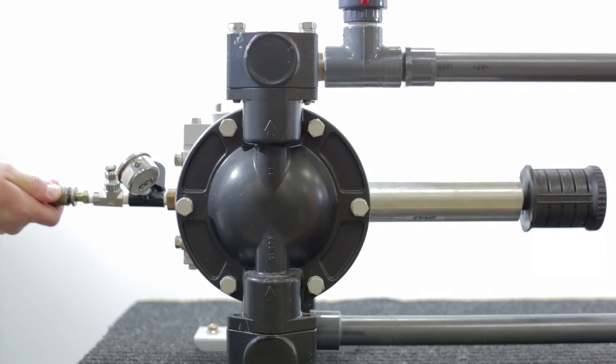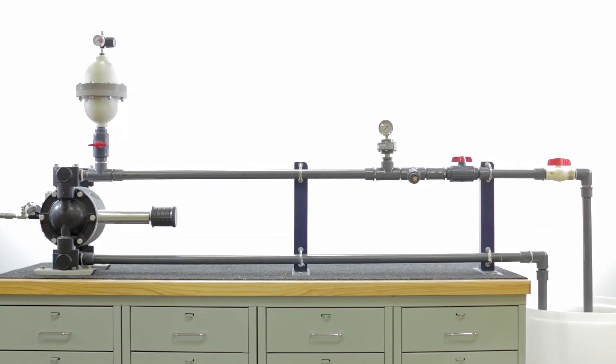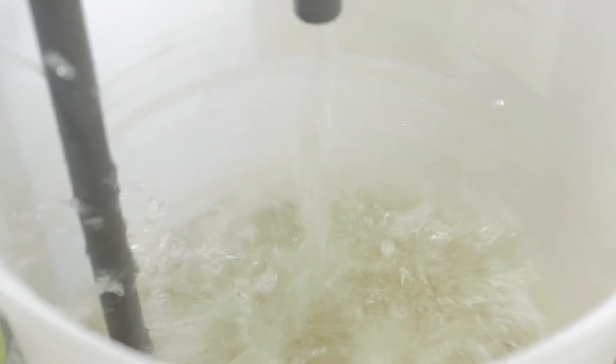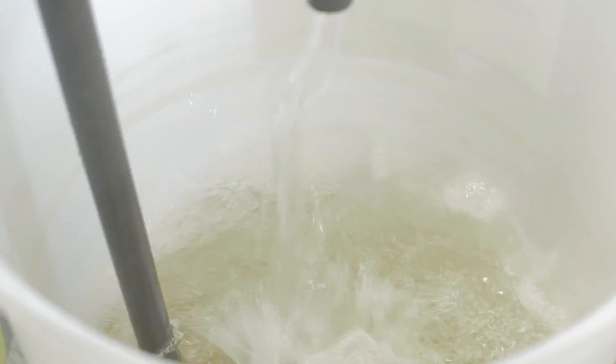When I turn the pump on, you'll see the pipe shaking, vibrating, and a pulsing flow. This flow comes from the pump by itself without the dampener. You'll see the pipe vibrating and a pulsating flow is foaming and splashing the product.